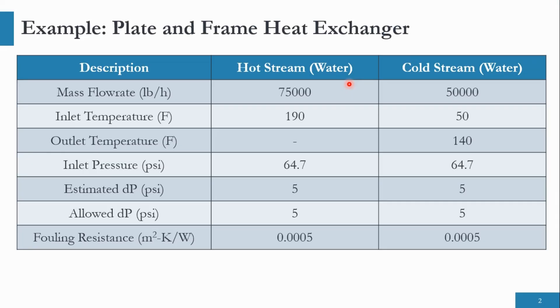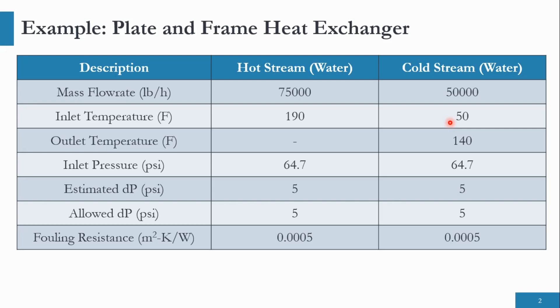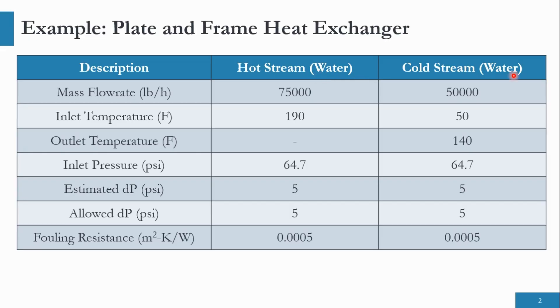We have been given the problem statement for plate and frame heat exchanger. The mass flow rate in pounds per hour for hot stream is 75,000 while for cold stream it is 50,000. The inlet temperature of the hot stream is 190 degree Fahrenheit; outlet is not given. Inlet temperature of cold stream is 50 degree Fahrenheit while outlet temperature is 140 degree Fahrenheit. The inlet pressure of both cold and hot streams are 64.7 PSI. The estimated and allowed pressure drop for both are 5 PSI each. Fouling resistance for both is 0.0005.